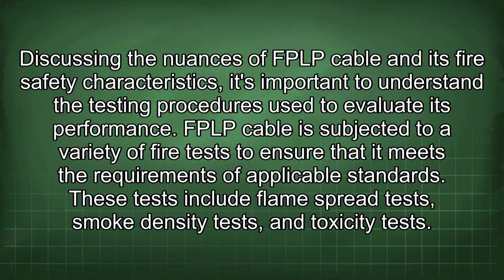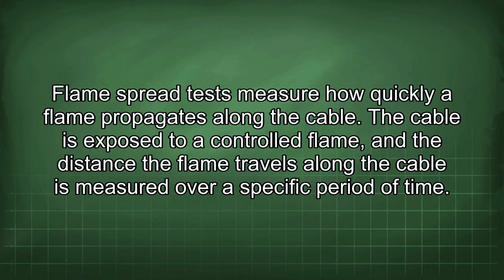FPLP cable is subjected to a variety of fire tests to ensure that it meets the requirements of applicable standards. These tests include flame spread tests, smoke density tests, and toxicity tests. Flame spread tests measure how quickly a flame propagates along the cable.